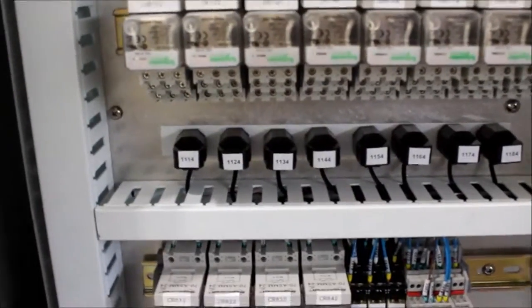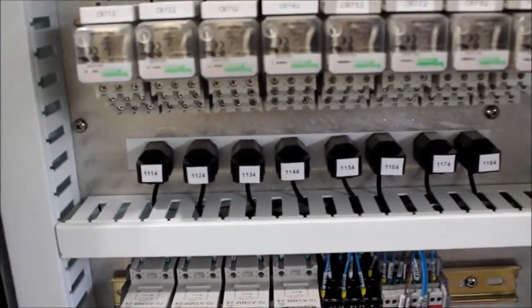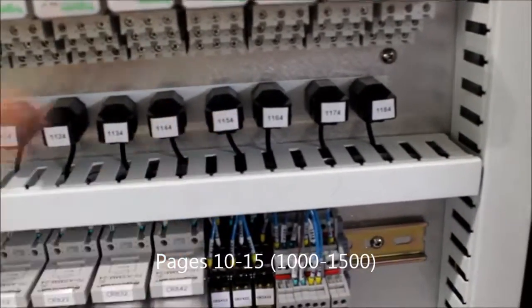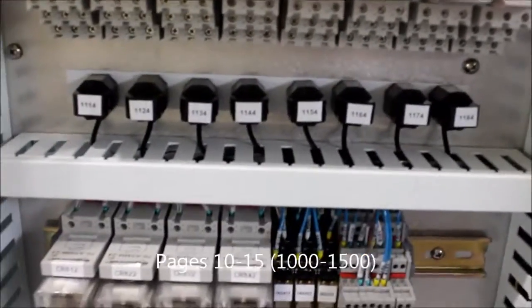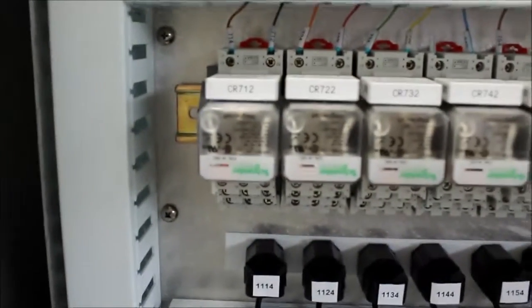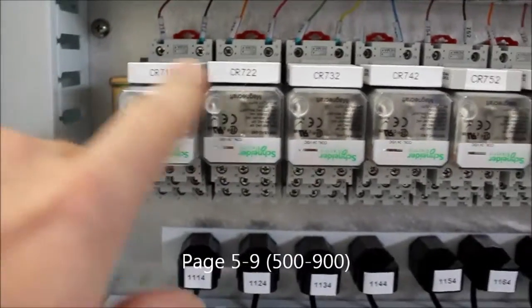The individual subcircuits within the residential structure are each monitored through a set of CTs. For example, this bank of CTs is numbered 1100. There is a corresponding page on the system schematic, 1100, with those CTs. In this case, we just number them house loads 9 through 16 because we don't know yet what loads those will be connected to. But that is configurable in our API so that those are mapped to known circuits within the house. And there are corresponding relays for each one of those loads here.